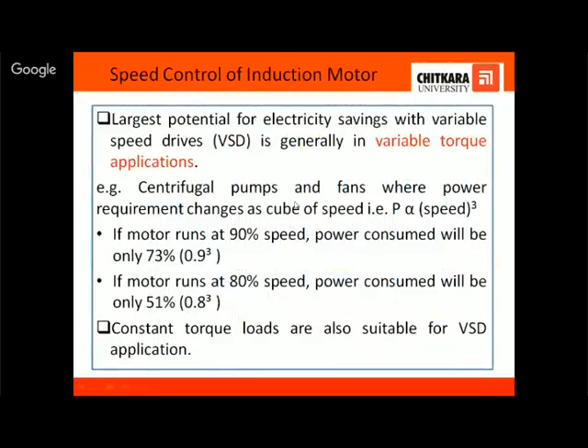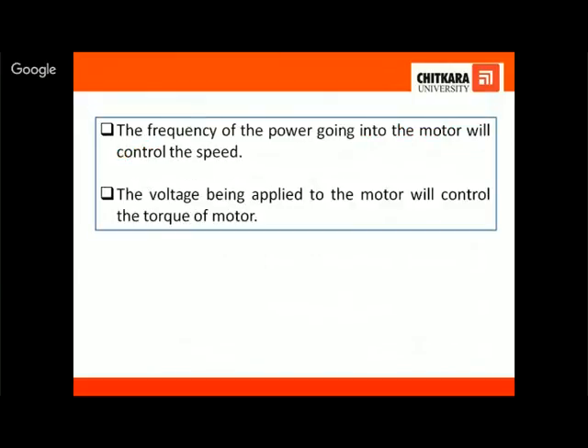So the largest potential for energy saving is with the variable speed drives, and it finds application in variable torque applications, that is centrifugal pumps and fans, where the power varies as the cube of the speed. I will give you a small example. If the motor runs at 90% speed, power consumed will be 73%. If the motor runs at 80% speed, the power consumed will be only 51%. Although constant torque loads are also suitable for variable speed drives.